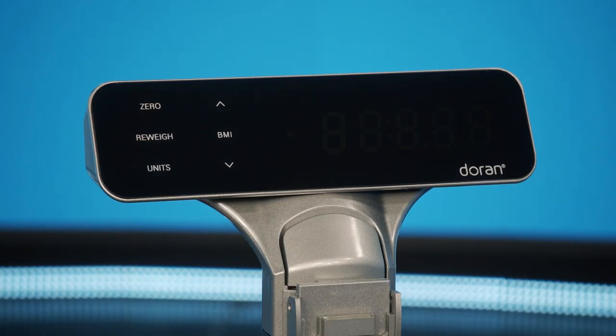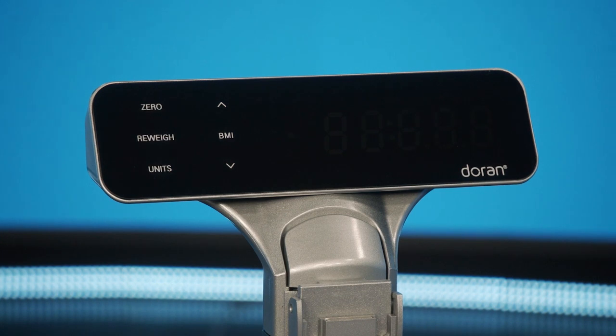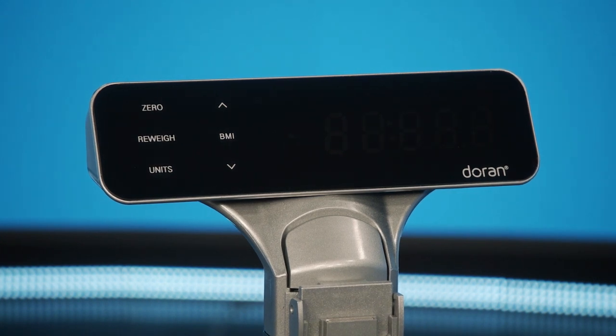We suggest that you use calibrated test weights when calibrating and evaluating the scale. Only calibrated weights are a good reference. Comparisons to other scales may or may not be accurate depending on that scale's condition and calibration. Our scales leave the factory with an accurate calibration that will last the life of the scale if treated properly.